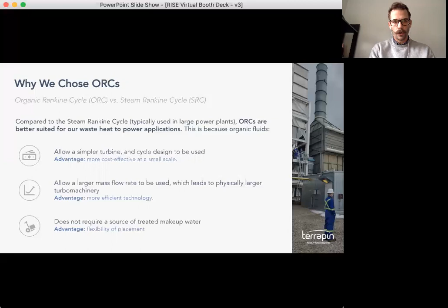Terrapin focuses on ORC power generation versus steam power generation because the properties of the organic fluid allow a simpler turbine and cycle design, which is more cost-effective at a smaller scale. The organic fluid also allows a larger mass flow rate, leading to physically larger turbo machinery that is inherently more efficient. And organic fluids release less energy in an explosion in the rare occasion of a catastrophic failure.